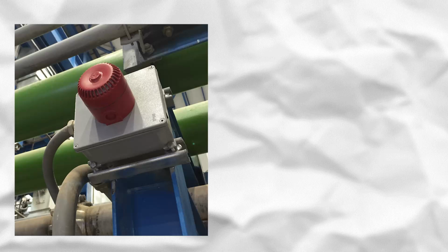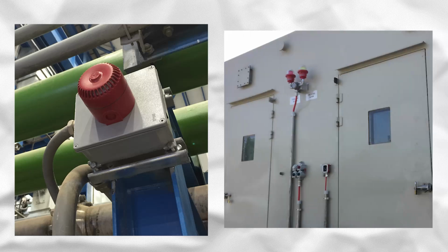About warning devices, the sound made by outdoor acoustical sounder must be at least 110 decibel, and flashers must be xenon type, and its illumination must not be less than 65 candela. Moreover, the cone of vision is 360 degrees.